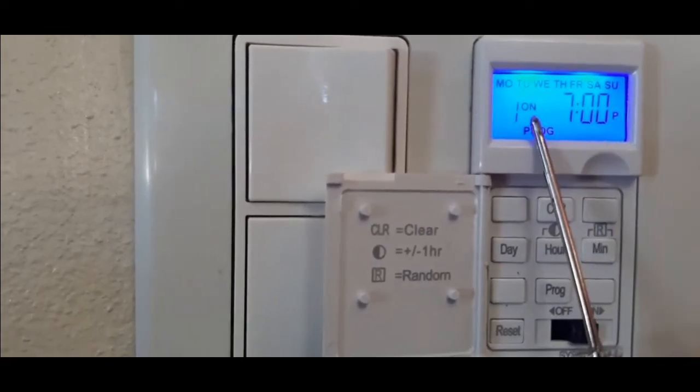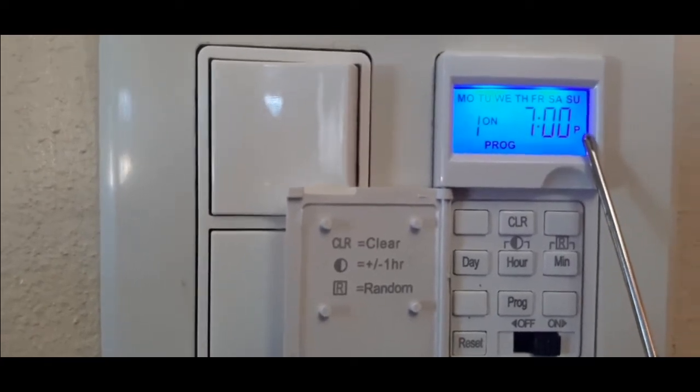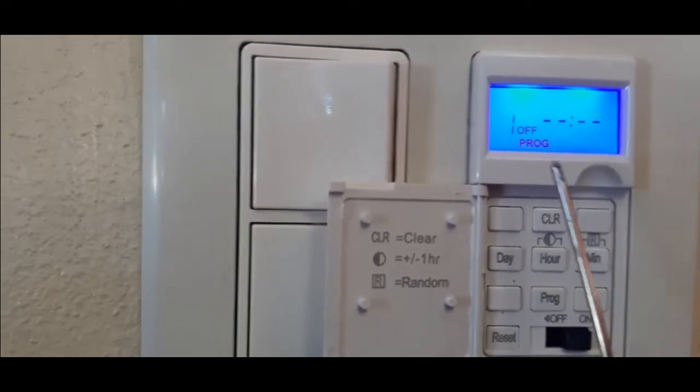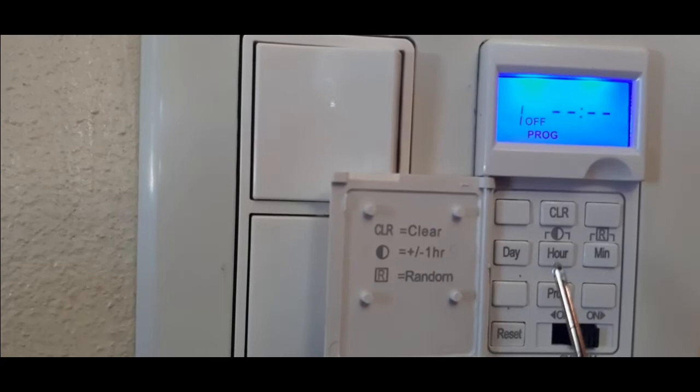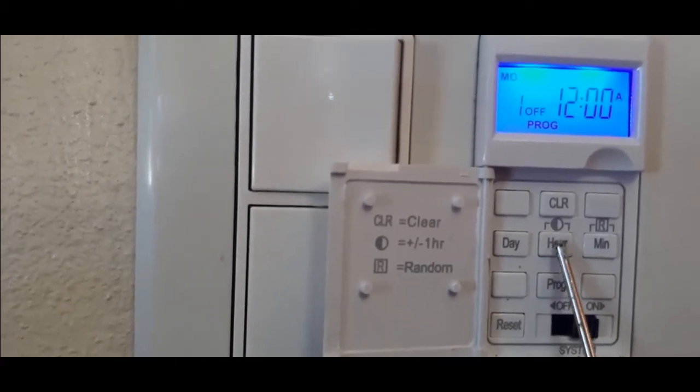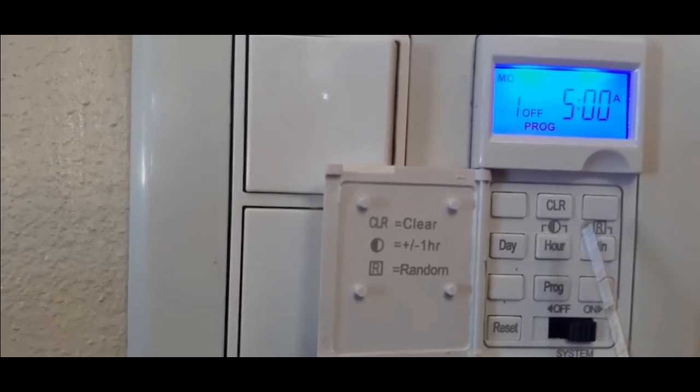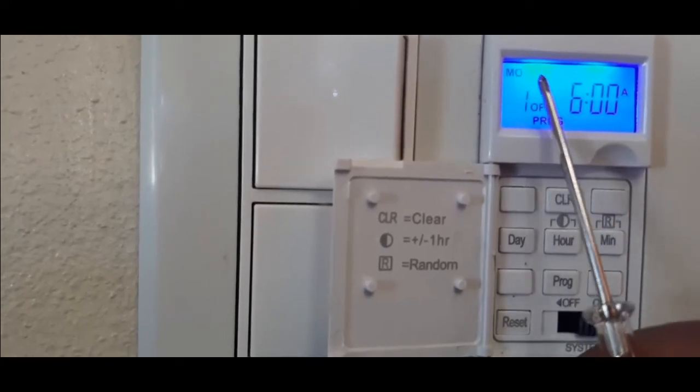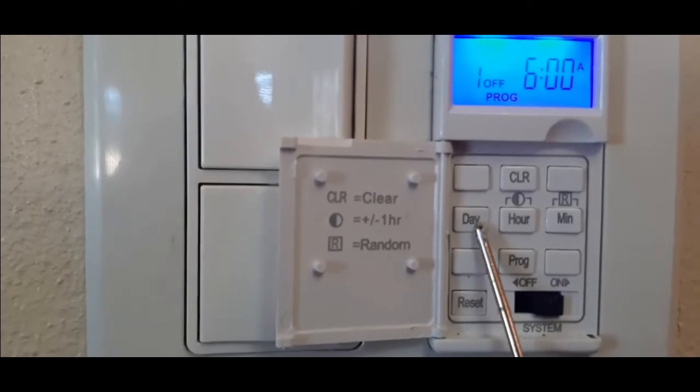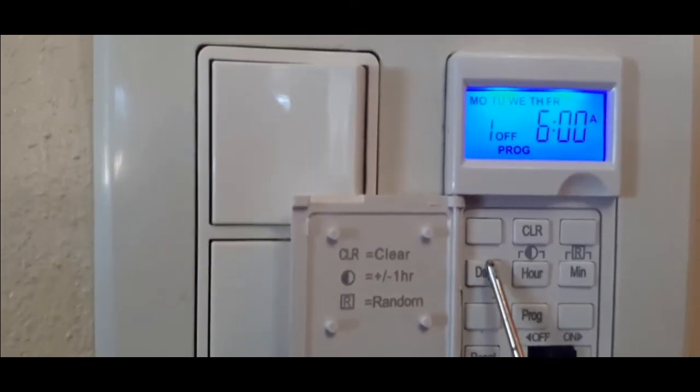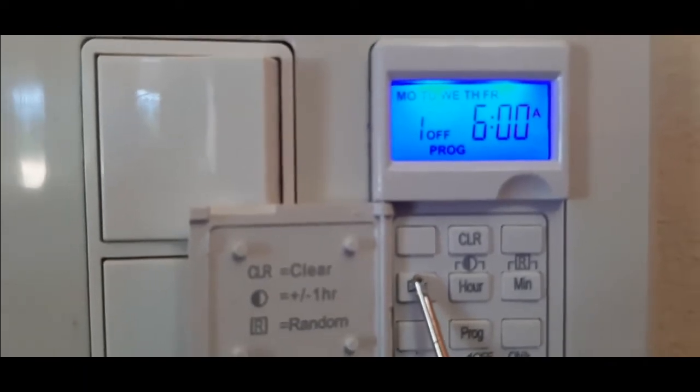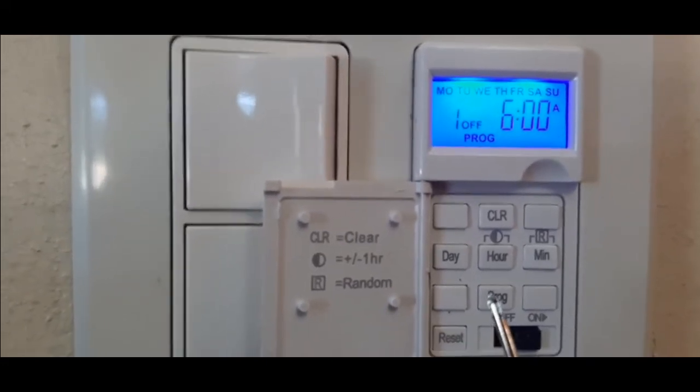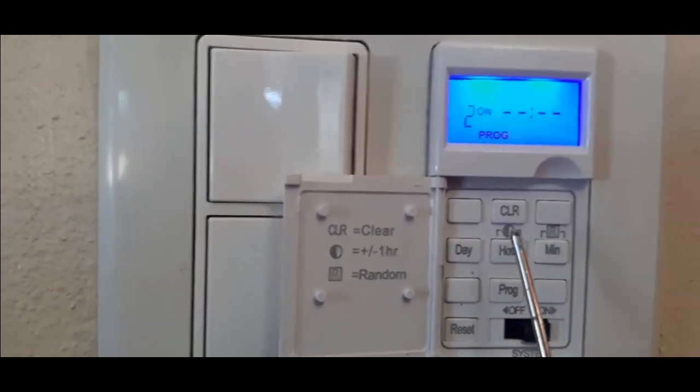And then I will program it again. Make sure the PM is there, or it will come on at 7 AM. So program it. This is the off time now. This represents the first programming mode or option. I want it to come off maybe around 5, 6 AM in the morning, and every day of the week. I'm going to do any specific day, not Monday to Friday, but I want it to come on and off on the weekends as well. And then you hit program again.